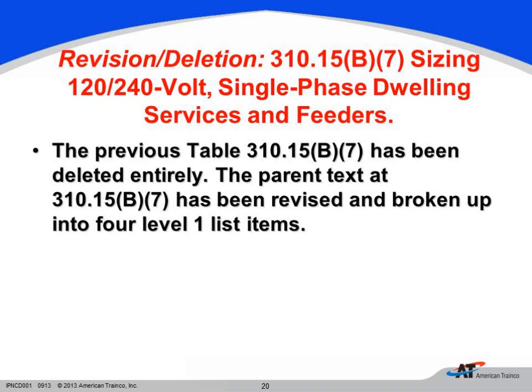So once we go through Article 220 and we add in the square footage and the small appliance circuit, the laundry, the specific appliances that we might have, and we get our total load, we're now going to have to multiply that by 83%, and then we're going to have to go back to 310.15(B)(16) and get the appropriate size conductor and match it up to one of those available choices the manufacturer gives us for our panels.